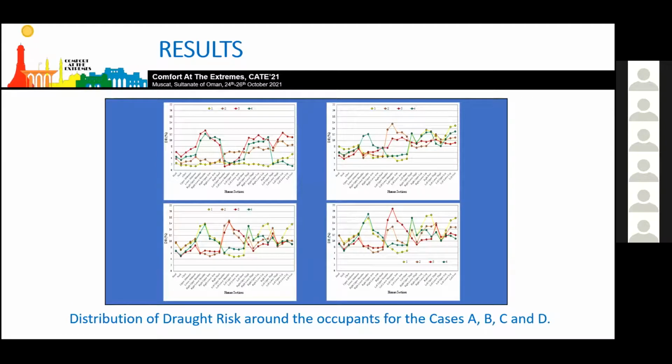These pictures show the draught risks that the occupants are subjected to. The draught risk is higher in the lower human body sections and increases when the airflow increases. However, these pictures show that the draught risks are in accordance with the international standard.